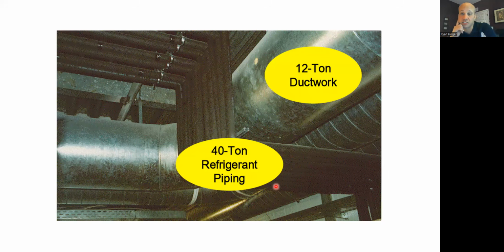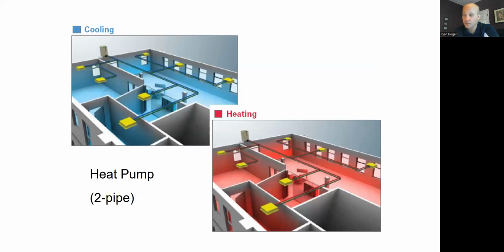That means this kind of system is really nice for retrofits where you don't already have ductwork. If you don't own ductwork, why are you even looking at putting ductwork in? So especially if you're converting a heating only building to cooling, this becomes a pretty good option here. The two flavors we have on VRF, 2-pipe and 3-pipe.